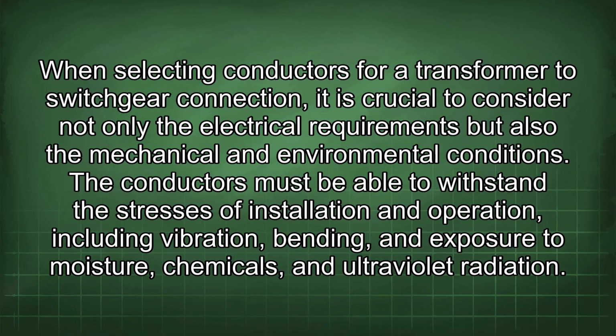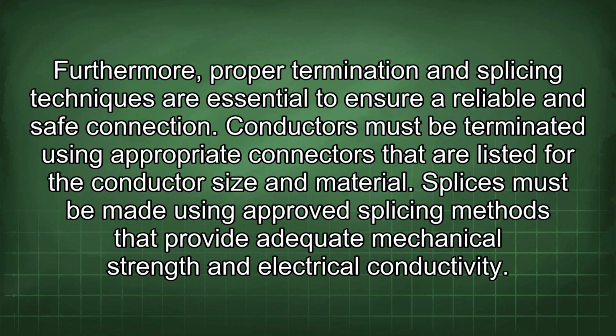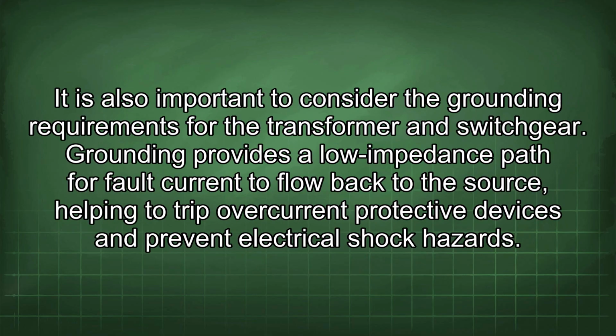The conductors must be able to withstand the stresses of installation and operation, including vibration, bending, and exposure to moisture, chemicals, and ultraviolet radiation. Furthermore, proper termination and splicing techniques are essential to ensure a reliable and safe connection. Conductors must be terminated using appropriate connectors that are listed for the conductor size and material. Splices must be made using approved splicing methods that provide adequate mechanical strength and electrical conductivity. It is also important to consider the grounding requirements for the transformer and switchgear. Grounding provides a low impedance path for fault current to flow back to the source, helping to trip overcurrent protective devices and prevent electrical shock hazards.